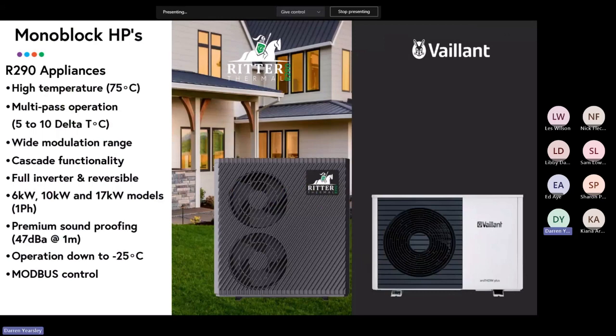And typically we run them in cascades. The reason for that is it gives you very wide modulation range and it gives you redundancy. So if we have a system which requires 80 kilowatts worth of recovery, typically we do that with 4 appliances. And that will give you a modulation range from one appliance on 30% output, which is its lowest modulation. They've got full inverter technology in them, is about a 6 kilowatt output. So you can continuously modulate your array from 6 kilowatts to 80 kilowatts, depending on demand. And so that does very, very well under both recovering your system where you need high power and then maintaining your system when you've just got ring main losses or very small hot water loads to serve. The system's very, very comfortable in doing that.